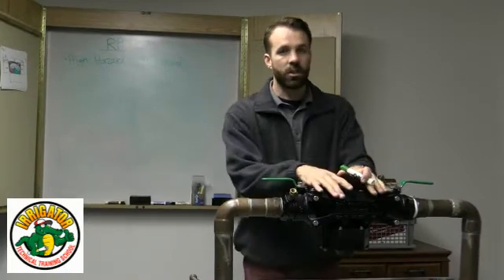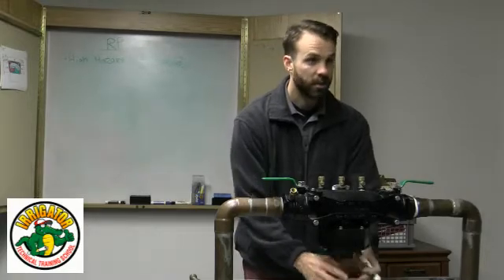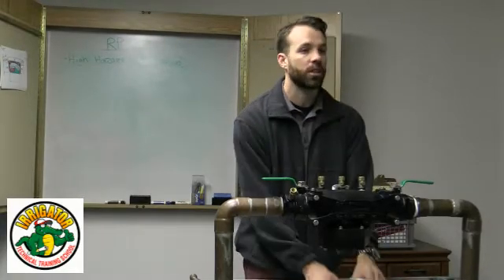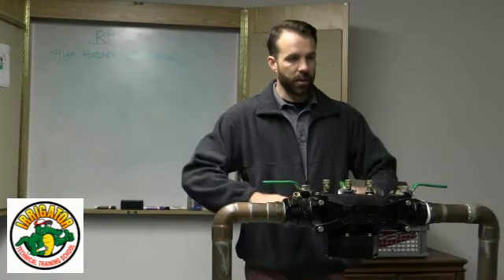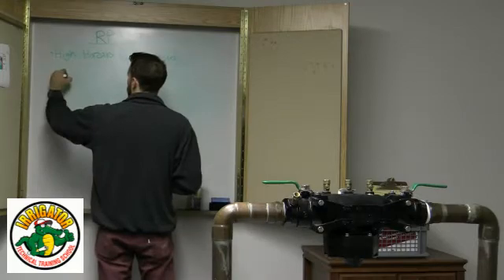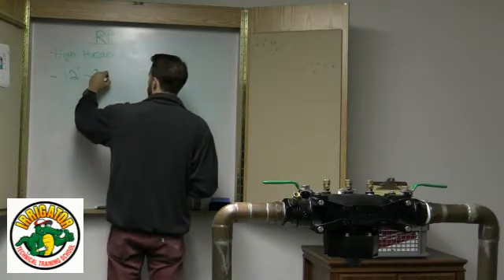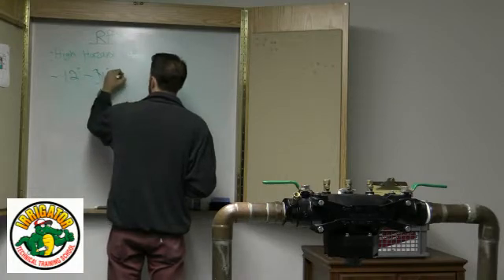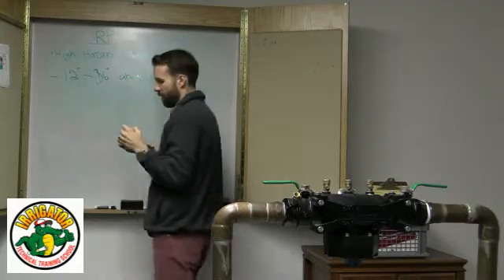To bring it to code, if we have a code, you actually have to have a drain, have it plumbed so that if it discharges, a drain will take the water out. Another thing is these have to be above ground. They have to be 12 to 36 inches above grade.